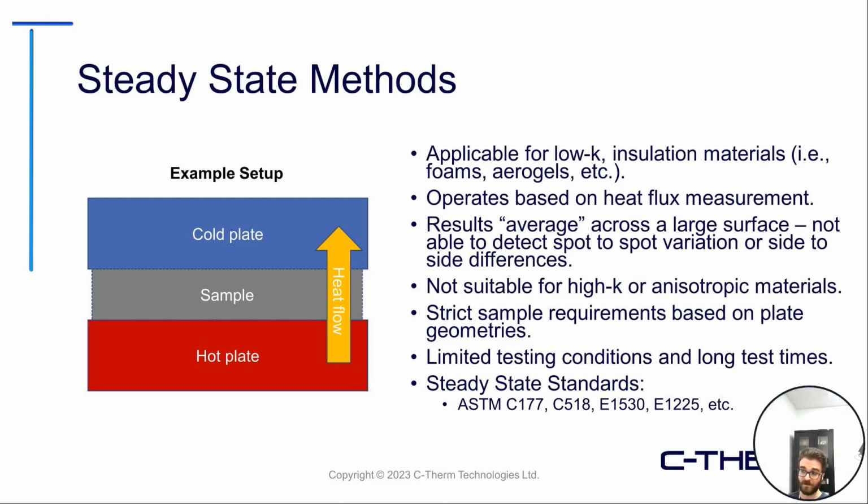length and width isn't unreasonable. The other thing that we'll highlight is your testing conditions are somewhat limited here. So doing representative testing in different humidity and environmental conditions, there's certain limitations there. And inherently they have longer test times, just simply related to how the measurement is performed.